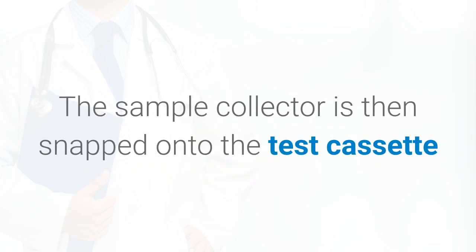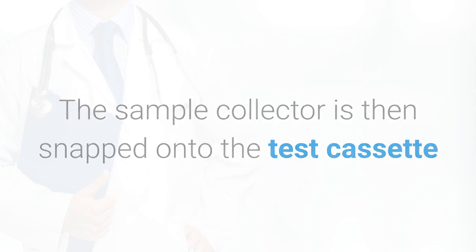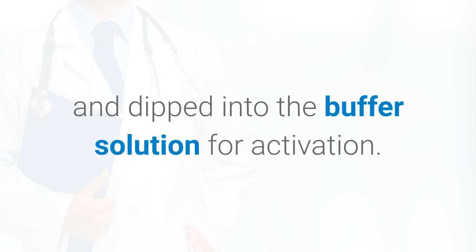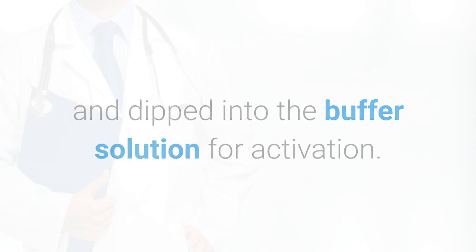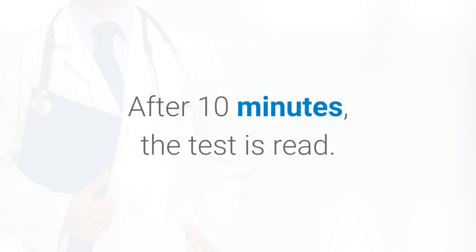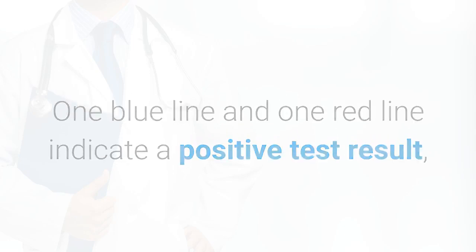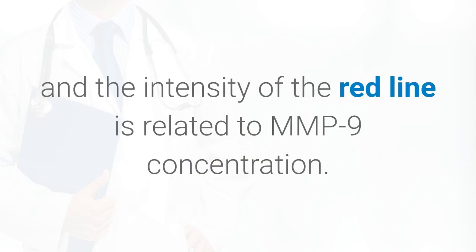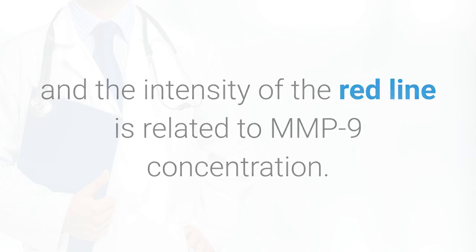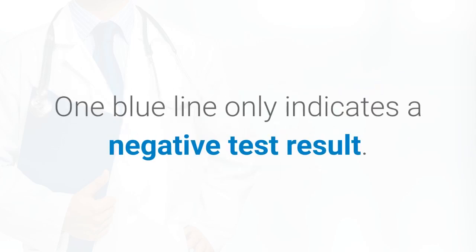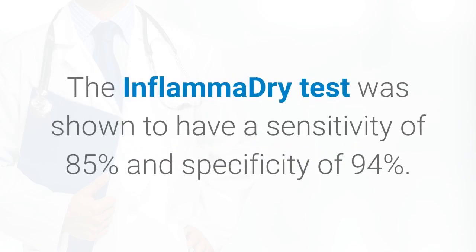The sample collector is then snapped onto the test cassette and dipped into the buffer solution for activation. After 10 minutes the test is read: one blue line and one red line indicate a positive test result, and the intensity of the red line is related to MMP9 concentration. One blue line only indicates a negative test result.